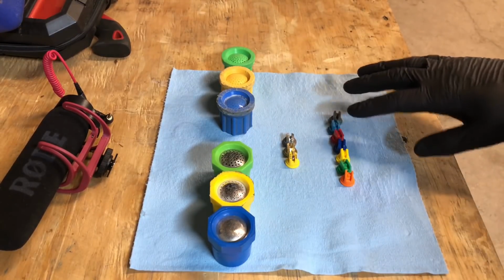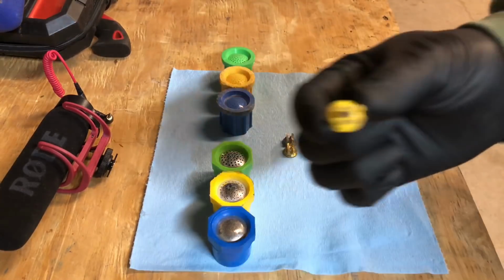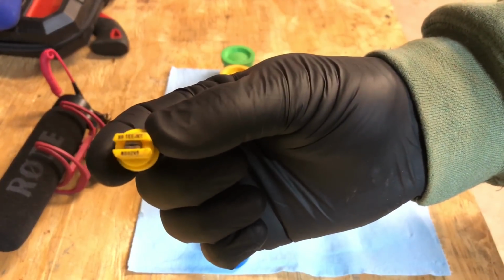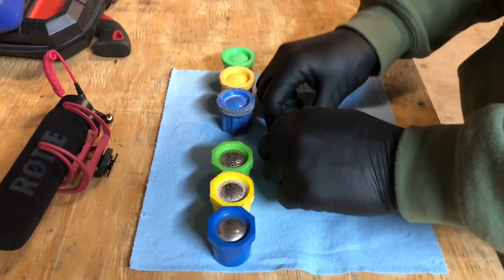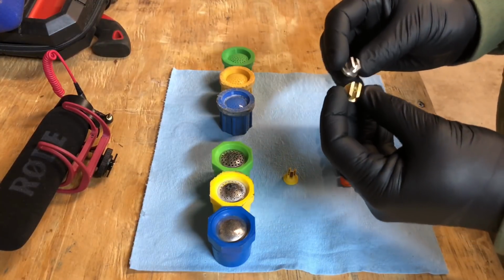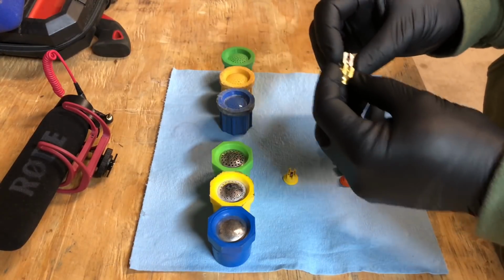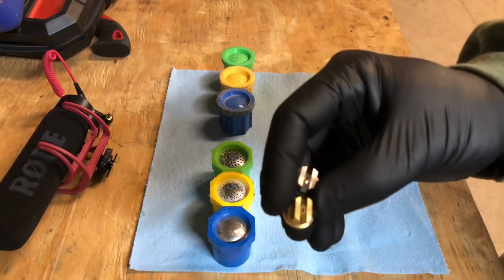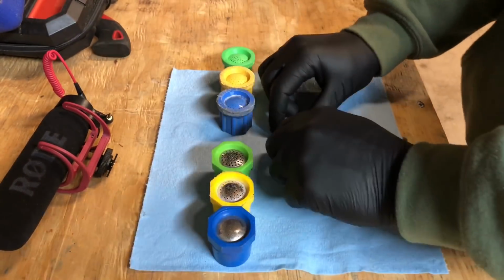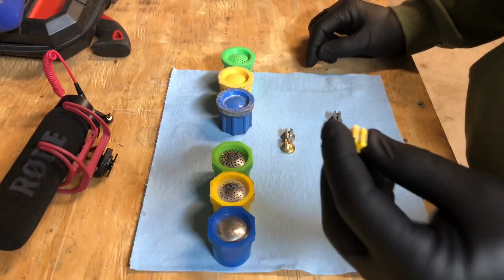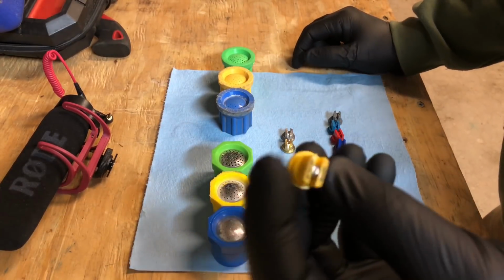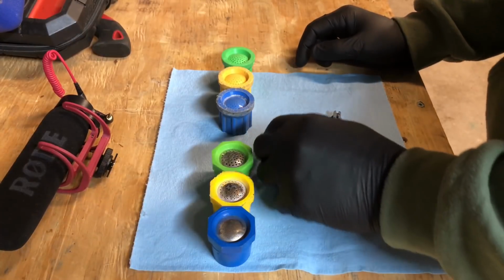We don't even use the plastic ones anymore. We prefer the one with the stainless steel insert. I like those over the brass or the stainless steel simply because they're cheaper than buying a solid brass one or solid stainless steel. And this stainless steel won't wear out over time, so your calibration stays consistent.